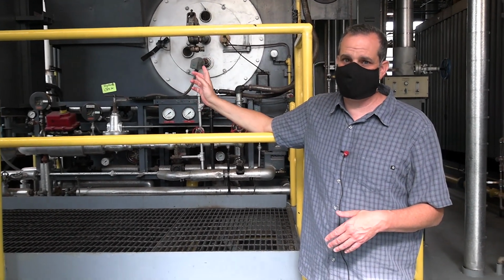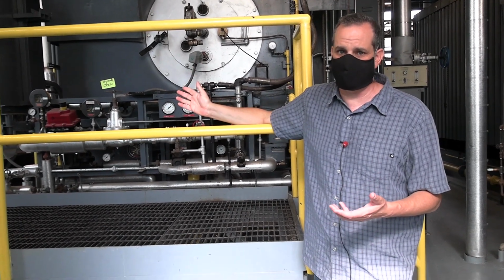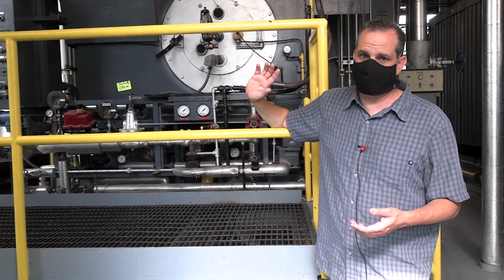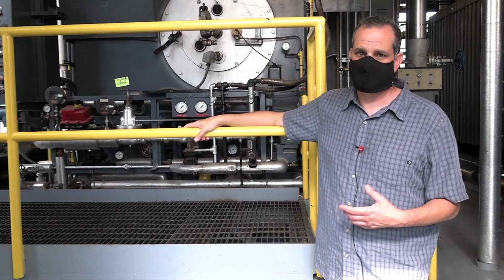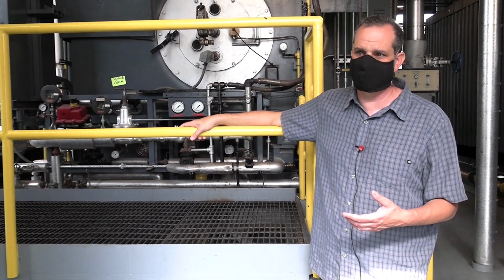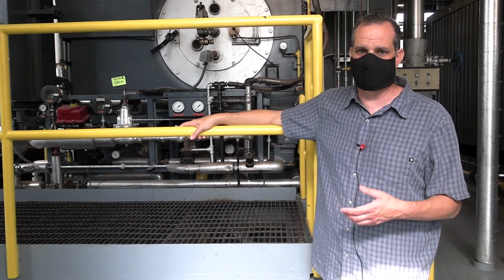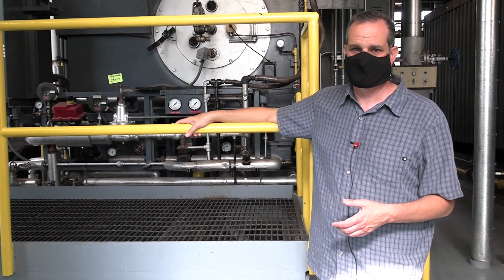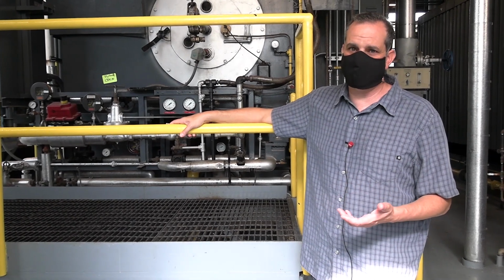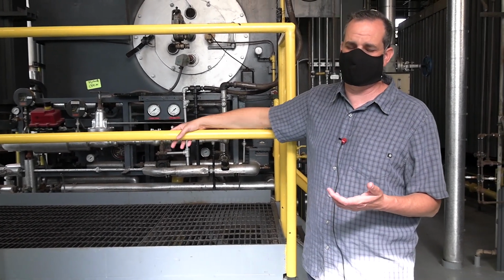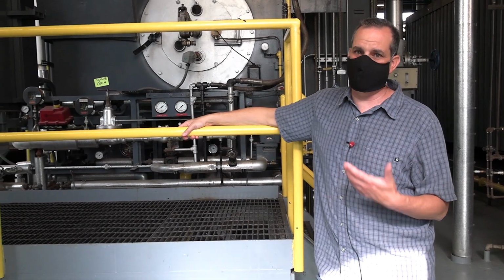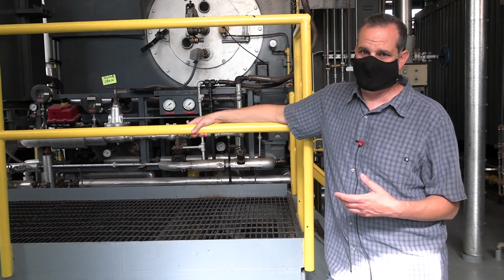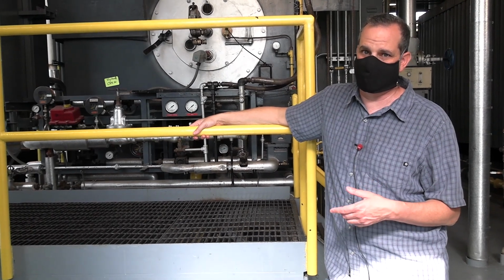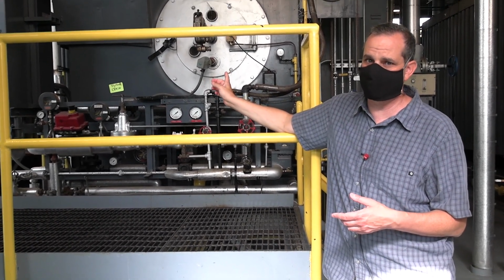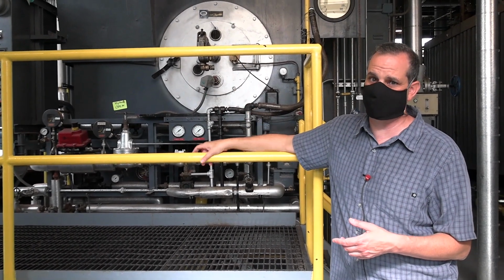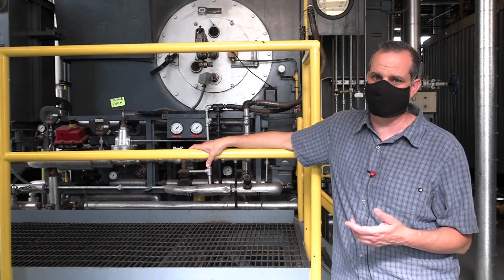If the natural gas system is interrupted for some reason, these 3 boilers can also burn number 6 fuel oil. We maybe do that for 1 or 2 days every couple of years when there's not enough gas in the system, but that's it. Prior to cogen being built in 2008, we used number 6 fuel oil all the time in 5 boilers at this location. These 2 are from 1972, and 3 older ones from the 1950s have since been removed.